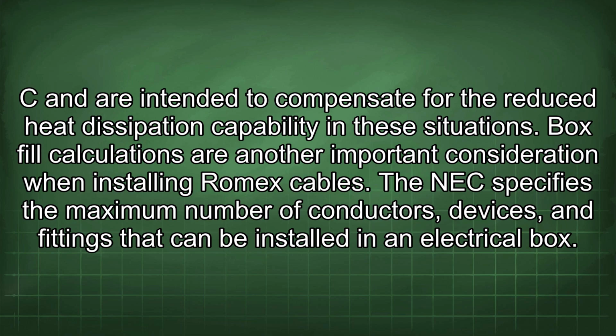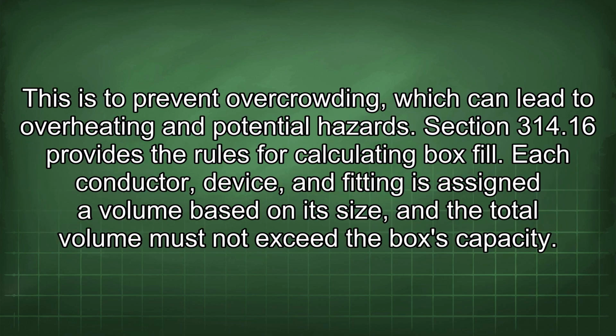Box fill calculations are another important consideration when installing Romex cables. The NEC specifies the maximum number of conductors, devices, and fittings that can be installed in an electrical box. This is to prevent overcrowding, which can lead to overheating and potential hazards. Section 314.16 provides the rules for calculating box fill. Each conductor, device, and fitting is assigned a volume based on its size, and the total volume must not exceed the box's capacity.